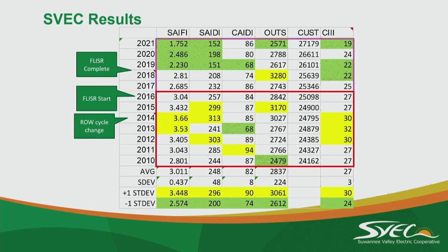But either way, we're backfeeding these in 45 seconds. That's good, but then you have to possibly wait another 45 seconds for the next one? Well, yeah, if you had two happen at one time. Well, they can be in different areas. If one feeder has to go all the way through a full backfeed, then you have another fault on that same feeder- but I could have two faults happening on our system, two different feeders, and they'll backfeed both of them separately.